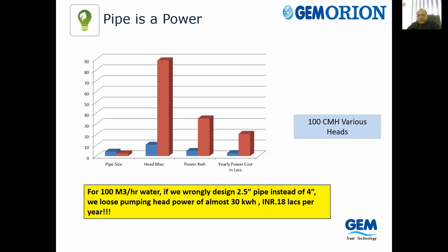And so these are some indicative ideas about piping. This piping is highly dependent upon the sizes. If the sizes are wrong, this gives a very rough idea, this is the ratio of difference between one pipe selected and one required. So when it's a small piping difference, there's a huge head difference in the piping, which results in very high energy cost.